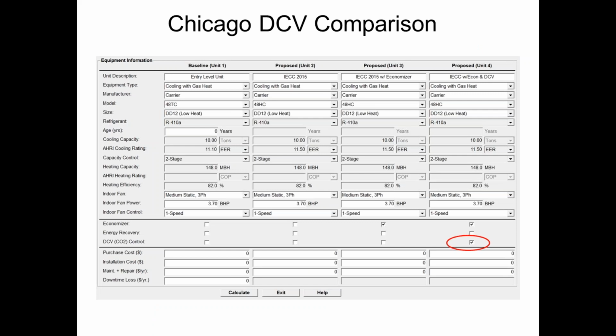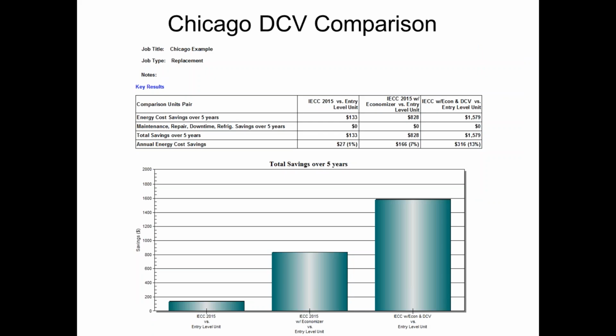So we'll add one more column on there: entry-level unit, code unit with economizer, and code unit with economizer and DCV. One more checkbox, right? That bumps us up to 13% savings. So just adding that CO2 sensor on top of the code-compliant unit with economizer was another 6% on top of the original 7% we were saving. And CO2 sensors are not that expensive, so there can be some significant energy savings there. Now, this is just a particular example. Some examples will save more than others, depending on how many people you have and how many of them are coming and going. But this is just an average office building scenario for my example.